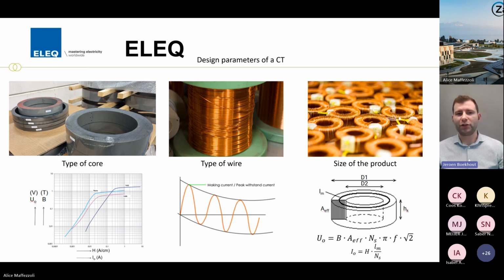A general rule of thumb is that the bigger the CT gets, the bigger the voltages it can supply, which means the higher the burden it can deliver the required current. In this case, as explained, we have the advantage of an LPCT. That means we need a voltage output, which can be achieved on a burden we can choose ourselves. And in this case, the total product burden is in the order of magnitude of 10 to the power of -4. So that means we have a very minimal impact and maximum opportunity for the core to supply the required energy, but also minimal impact on the tapped energy on the secondary circuit of the existing infrastructure.